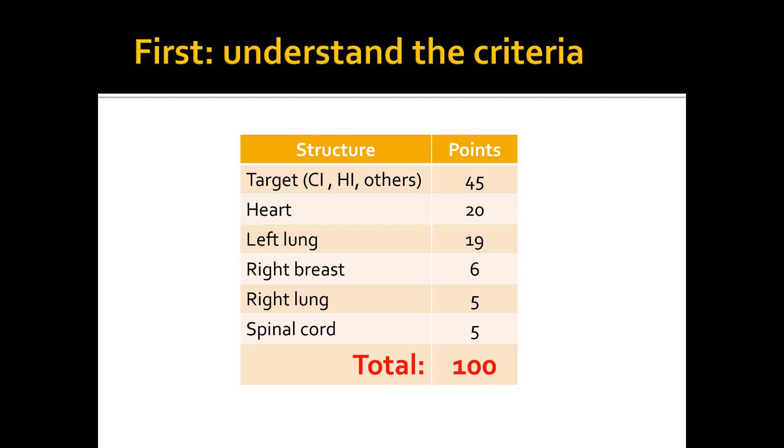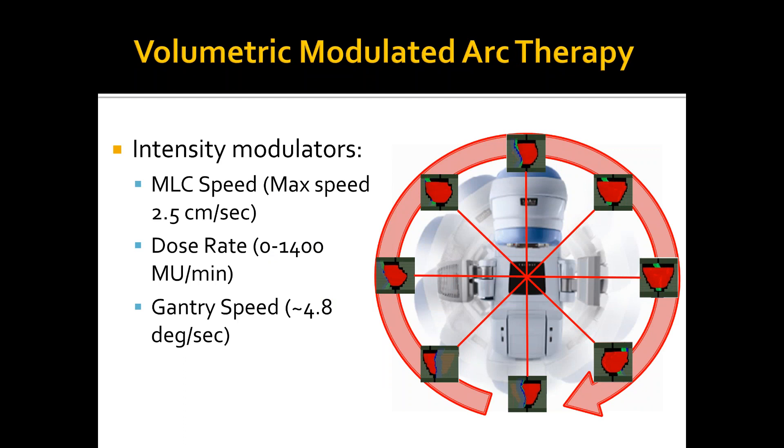A little bit about VMAT or volumetric modulated arc therapy. The gantry rotation is divided into control points. For Varian, there are about 178 control points in a full rotation. In this example, we see eight control points here. Each control point has different MLC speed with maximum speed of 2.5 cm per second, different dose rates from between 0 and 600 MU per minute or more than that for the case of triple F beams, and gantry speed, which is on average 4.8 degrees per second. The gantry speed can go less than that for the case that the dose rate is saturated. So the optimizer might want to push more dose from specific angles.